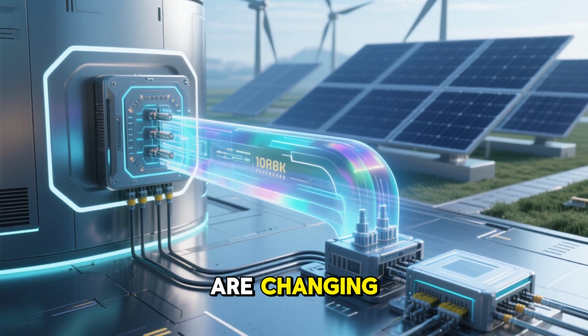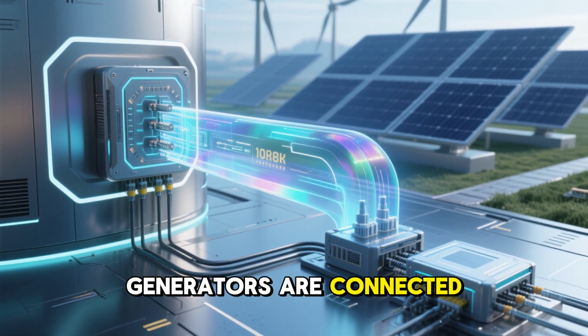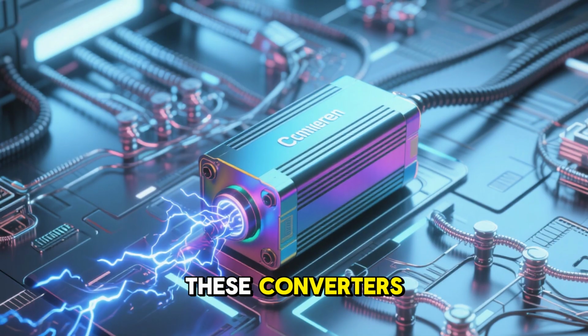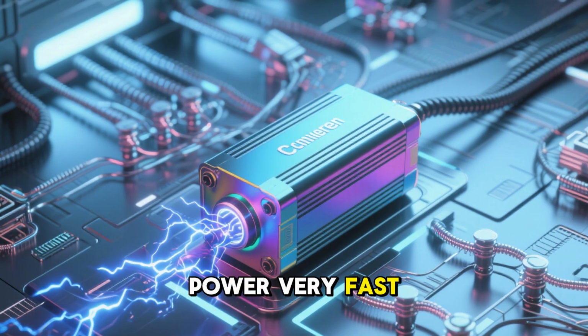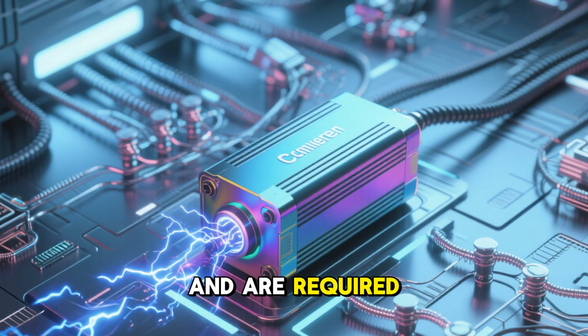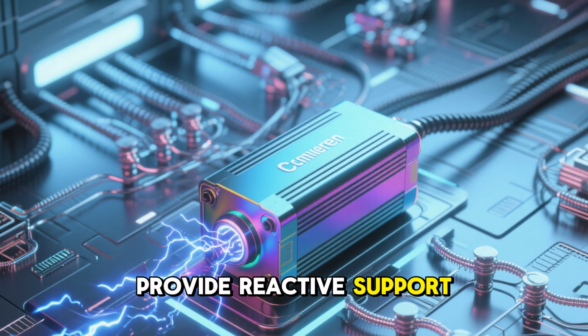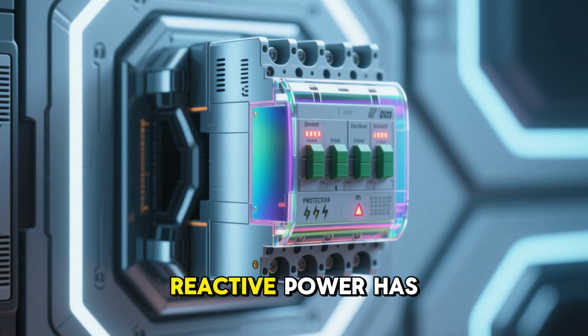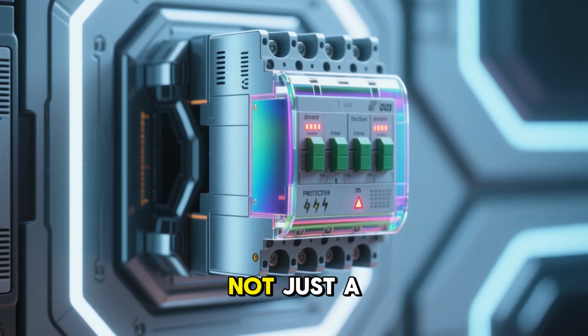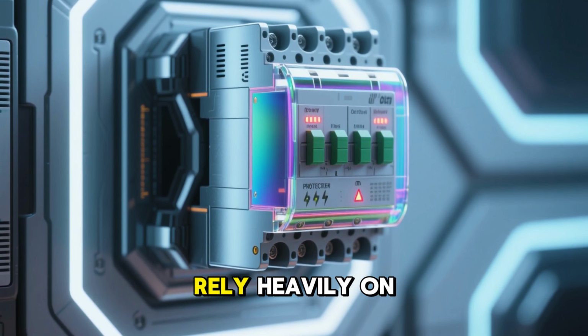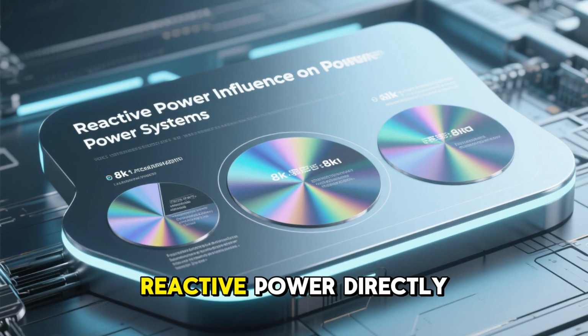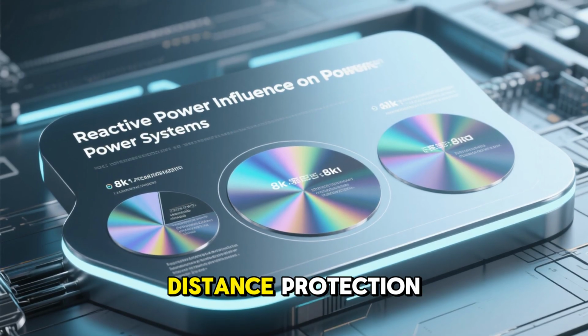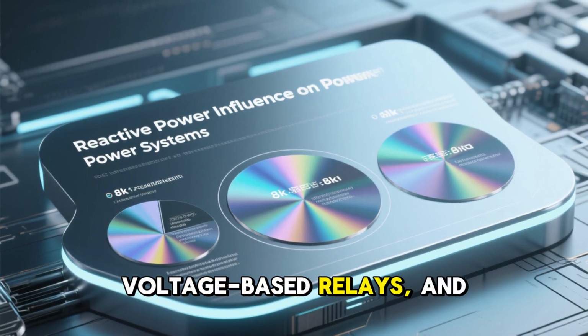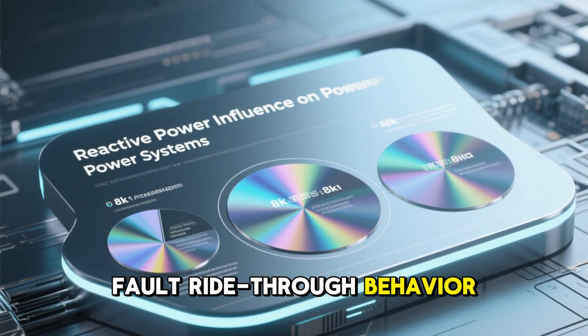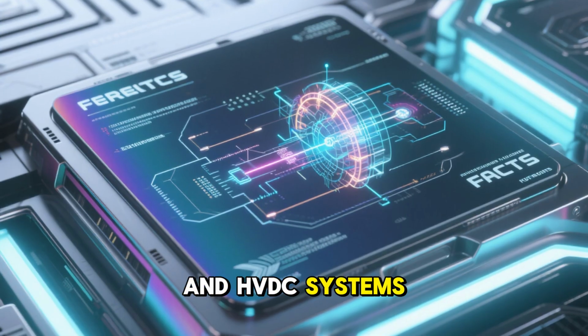Modern power systems are changing. Wind and solar generators are connected through power electronics. These converters can inject reactive power very fast, can support voltage during faults, and are required by grid codes to provide reactive support. Even at zero active power, reactive power has become a grid stability tool, not just a side effect. Protection systems rely heavily on voltage measurements. Reactive power directly affects distance protection, voltage-based relays, and converter fault ride-through behavior. In modern FACTS and HVDC systems, reactive current injection is often the first control action during faults.